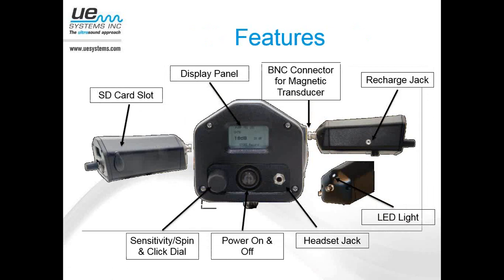Moving on here to the features of the instrument itself, you can see here we have the SD card slot. The beauty of having removable storage like this is you have the ability to go out and collect more than just one route at a time. If you want to collect several different routes, you could have multiple SD cards with different routes loaded on them. As soon as you take that SD card out, you just put another one in with a different route. It's going to automatically load it into the instrument, and then you can pick back up and collect data on that route, collect all that data at one time, and then go back and download that individually from each SD card.